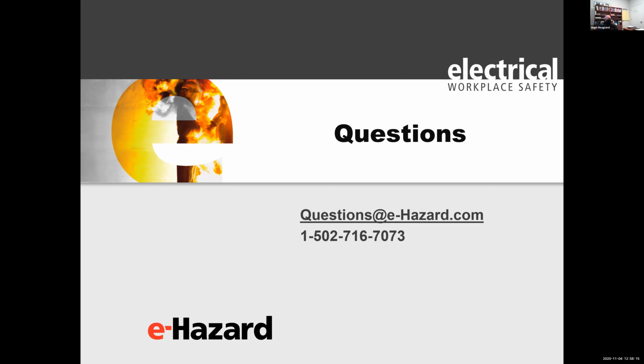Okay. Quick question here we got from our audience. Does arc-rated PPE have to have an FR rating? Well, arc-rated materials are automatically flame resistant. They don't have to meet NFPA 2112, which is a flash fire rating, but they have to be flame resistant. But by definition, if you meet ASTM F1506, or if you meet the IEC 61482-2 standard and you have an arc rating on it, then it is flame resistant. That's part of those specifications.